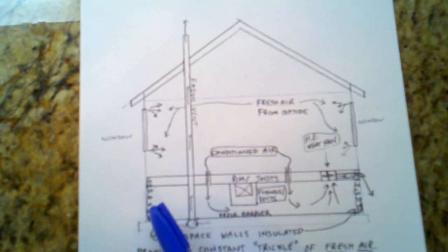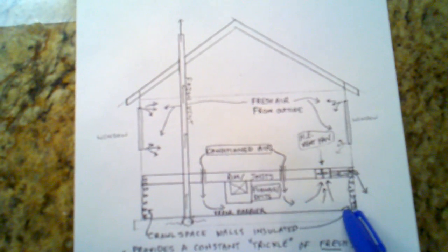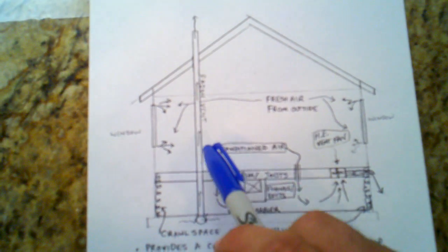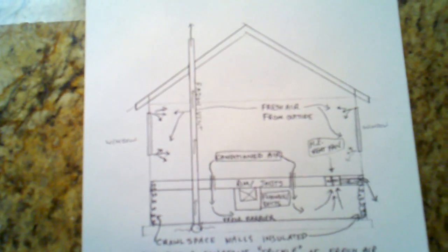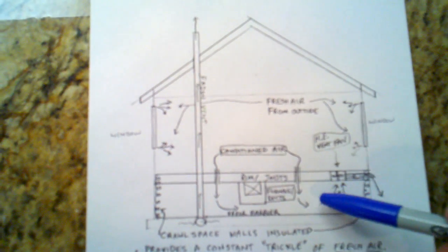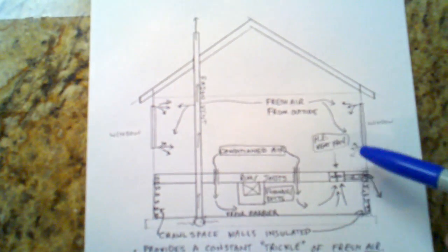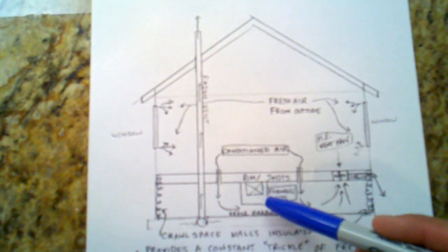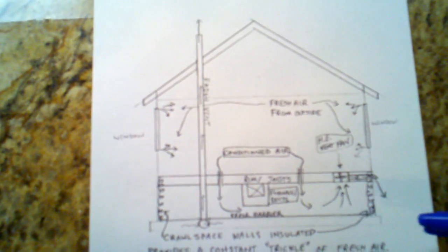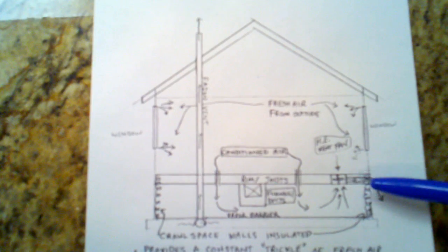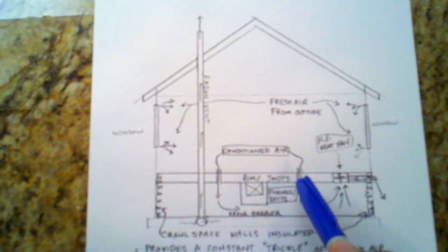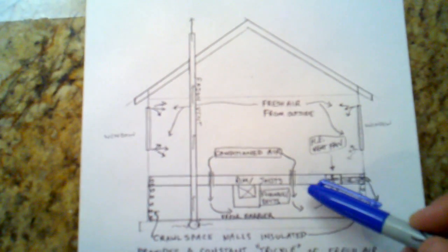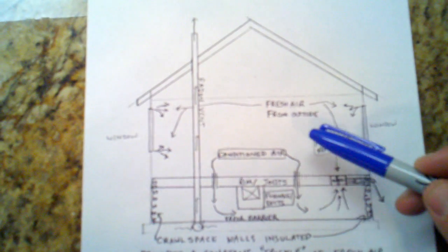Another thing to point out here, we do have a vapor barrier along the bottom of the crawl space that catches any moisture or radon gases, and it vents out this radon vent pipe out your roof. So none of those gases ever come into contact with any of the air inside of your conditioned space here. We insulate the stem walls because now you've got conditioned air down here in the crawl space, and so your thermal envelope ends right here as opposed to on the last sketch where the floor joists are. So you also reduce the amount of cold floors you feel on your feet because the air down below is pretty much the same temperature as the air up above.